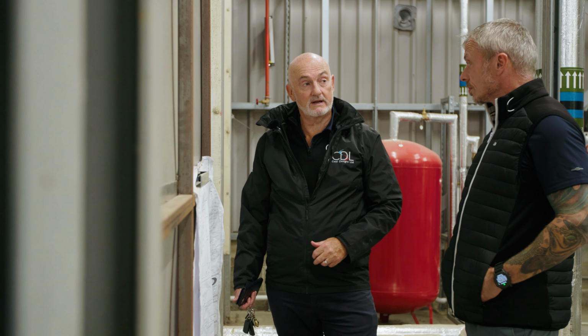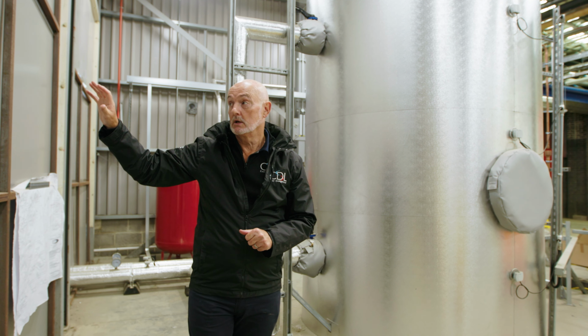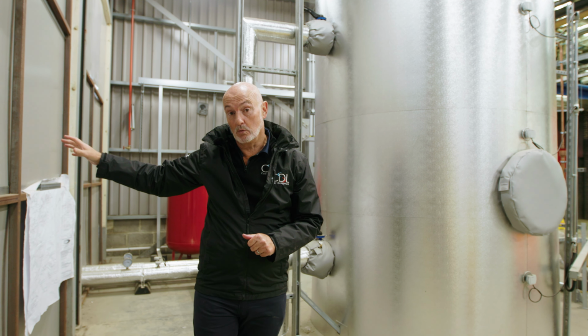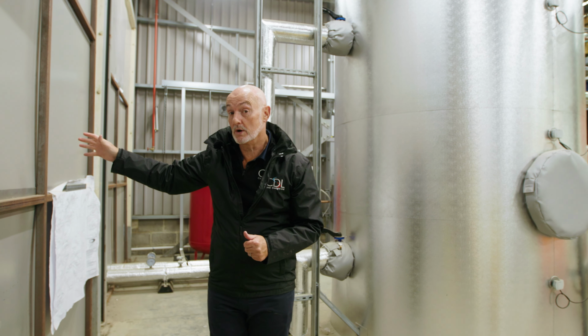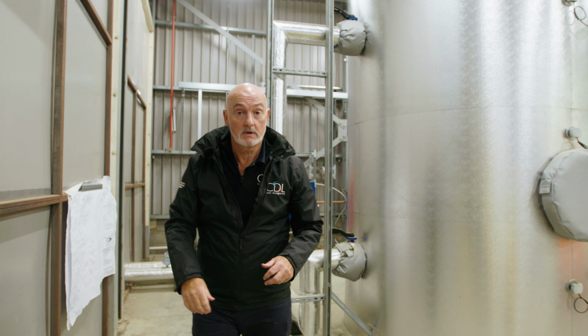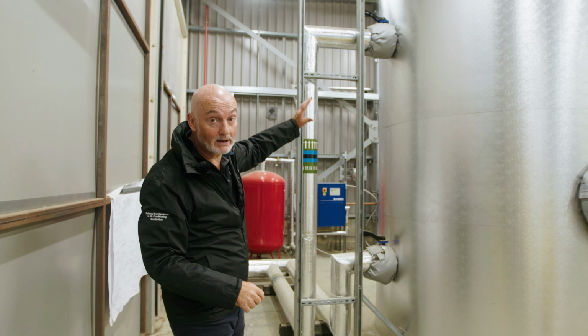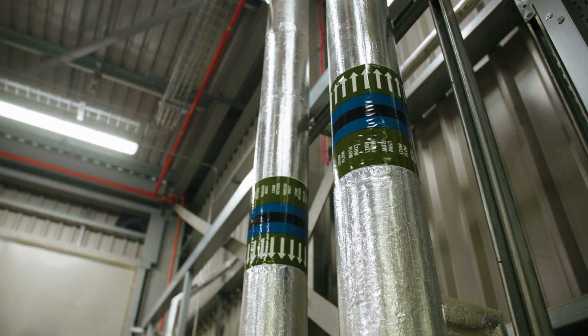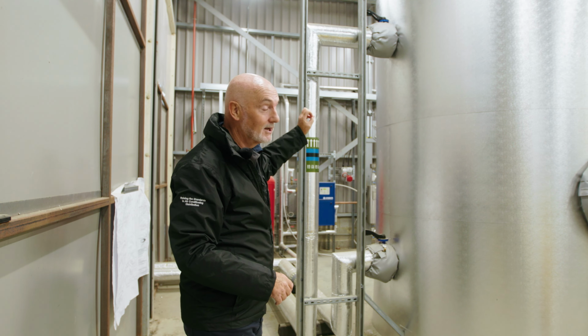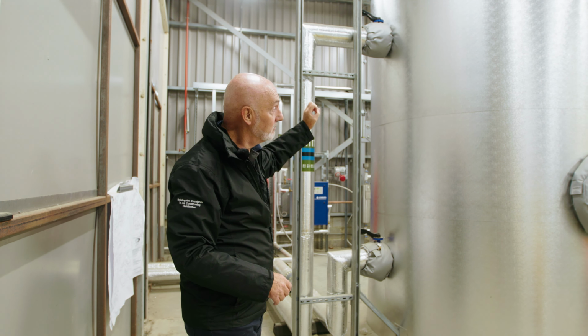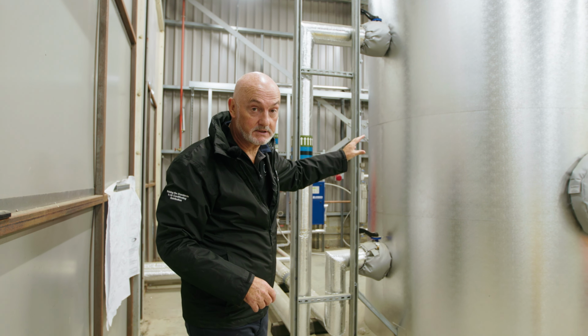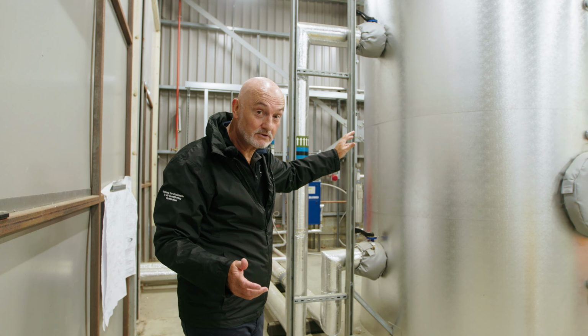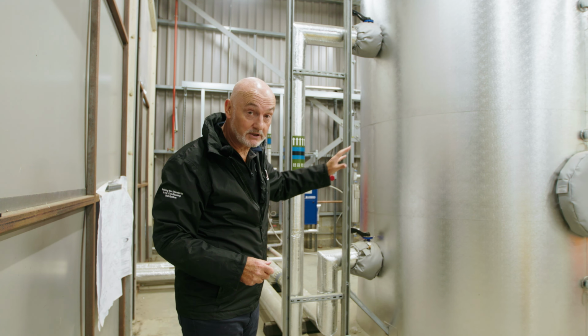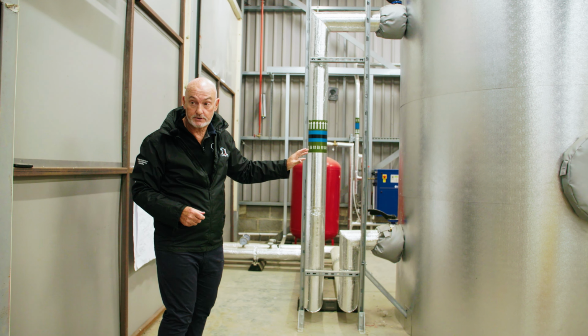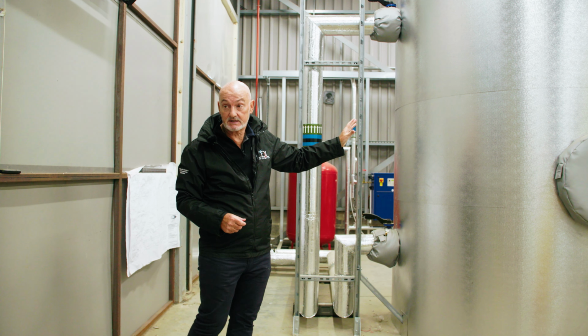Air source heat pumps outside generate the heat, placing the heat energy into the water at the desired temperature that we want, and it comes into the building on what they call the primary circuit, and this primary circuit comes to the buffer vessel. Mass is good. The more mass you have, the more balanced your system is. Unless it's domestic hot water, which is a slightly different issue, but when it comes to low temperature hot water, mass is good. This buffer is generously sized.